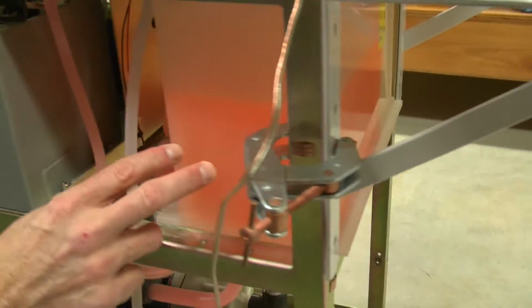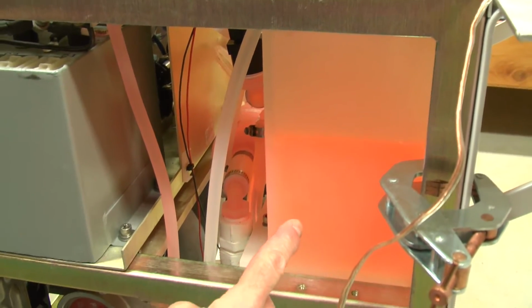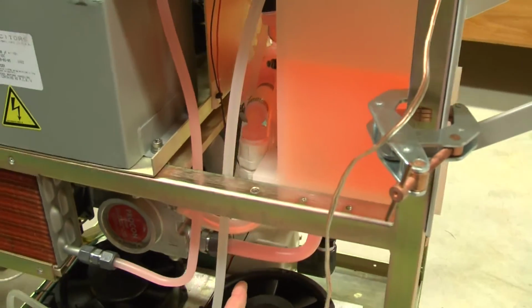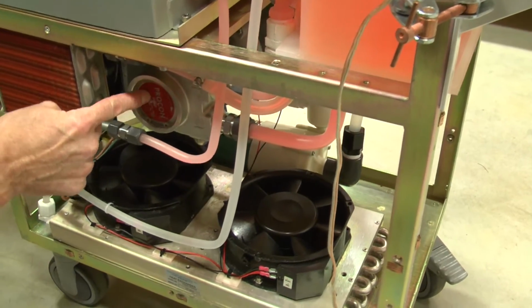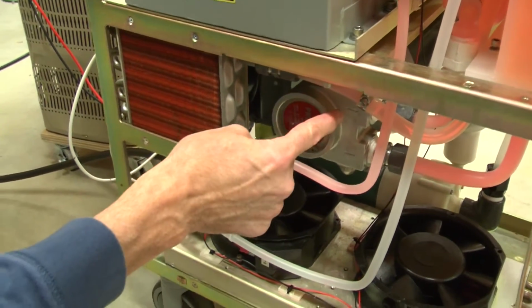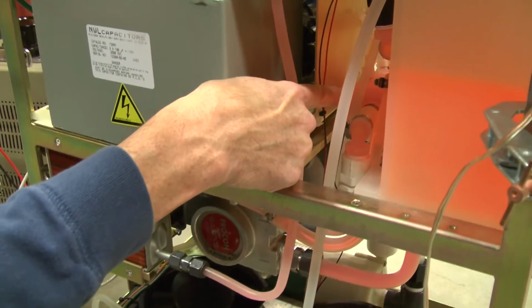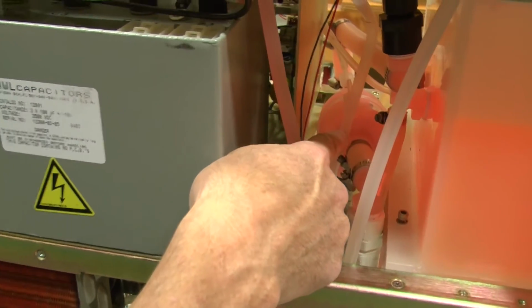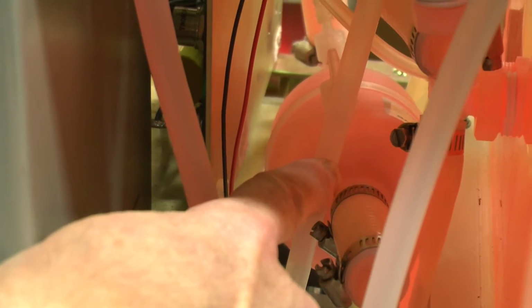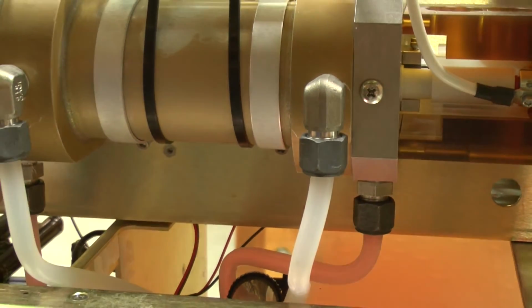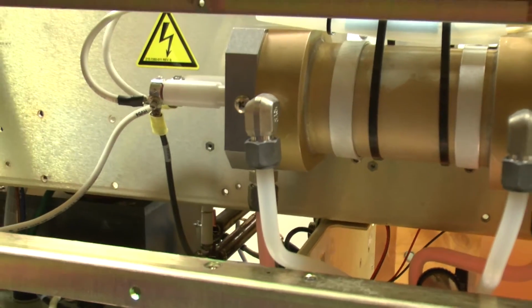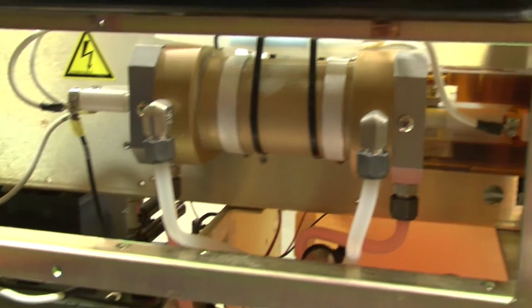On the dye side of the reservoir, the fluid is pumped out through a secondary pump. This pump then sends the fluid through a bubble filter. This 1 micron filter here is not really a particulate filter and certainly doesn't remove any of the dye, but removes some of the micro bubbles from the dissolved gas so that you don't get diffraction or a sort of fuzz or fog inside the laser tube. Then up through this high pressure line into the bottom of the head, out of the head to the radiator, which is fan cooled, and back to the reservoir again.